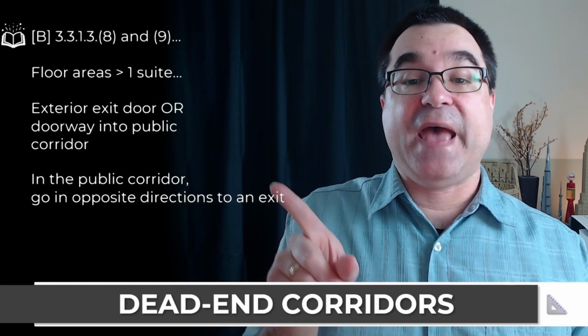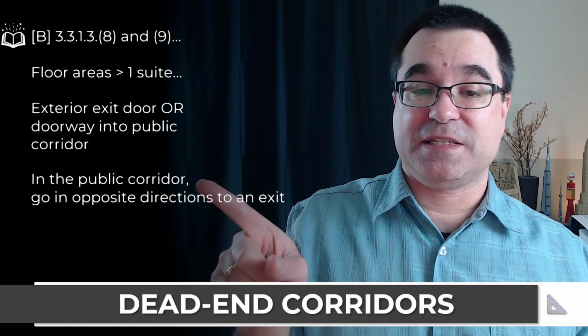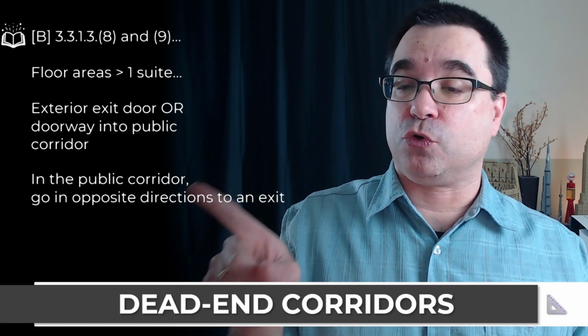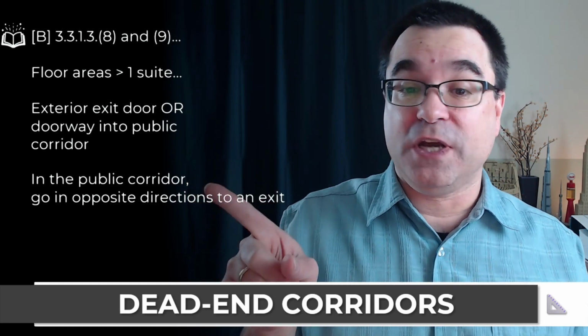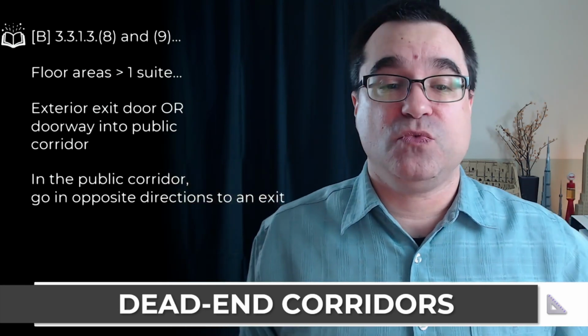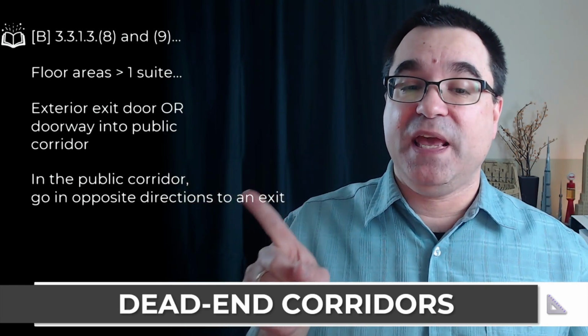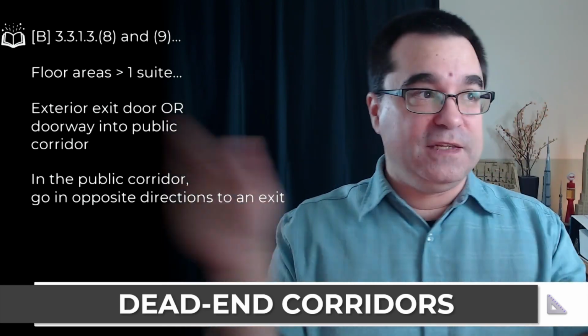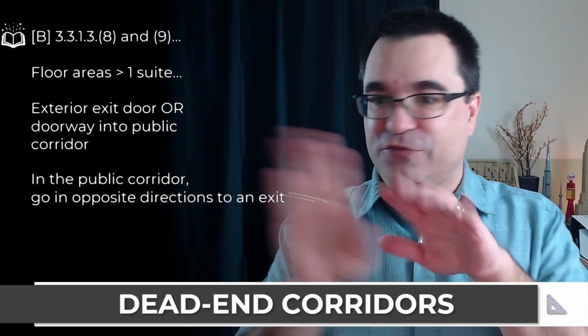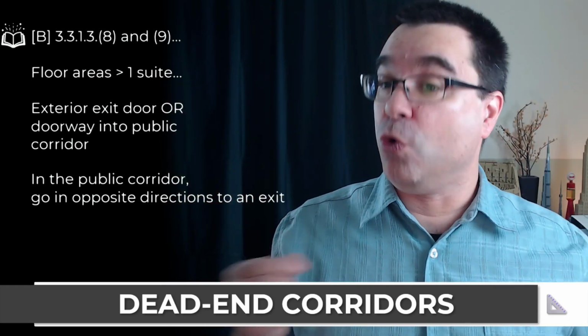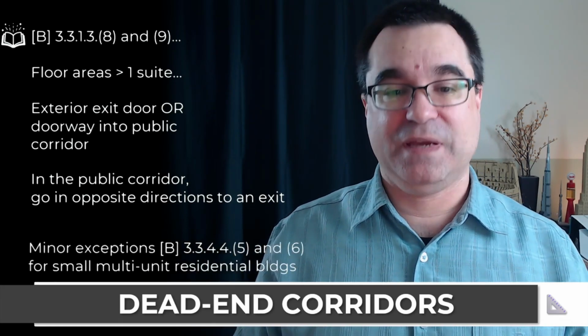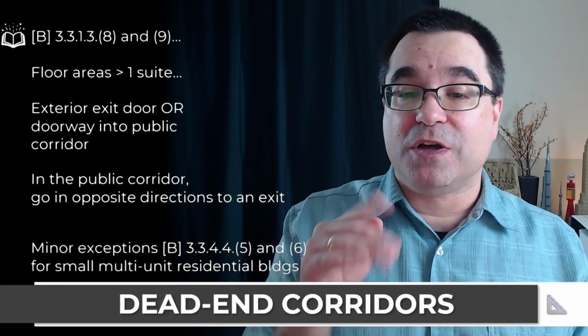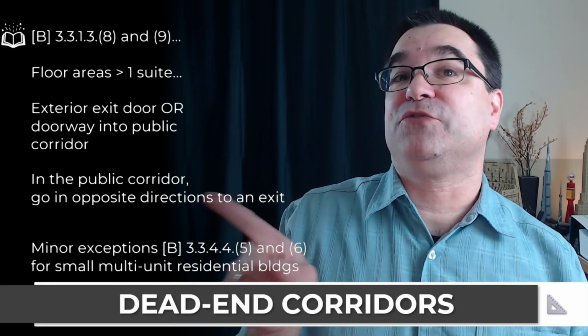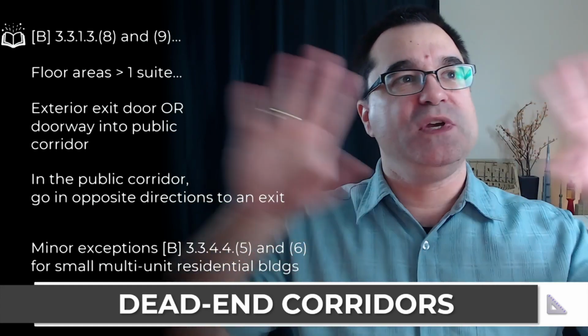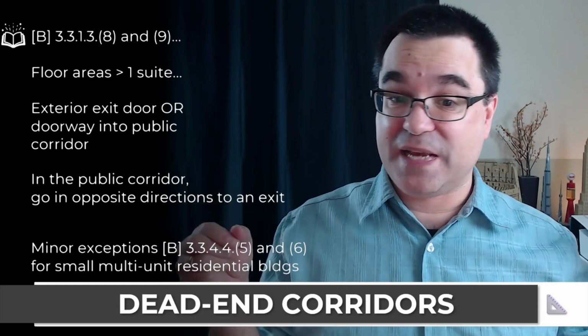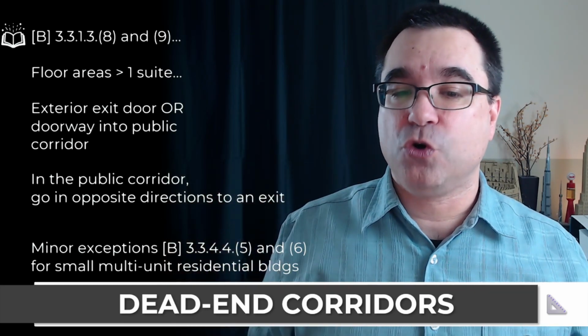And if you do choose to exit that suite into the public corridor, if that is your only option to exit that suite, you must be able to go in any direction in that corridor, so left or right, towards an exit. If that's not possible, if you cannot go left or right as soon as you exit your suite into the corridor towards an exit, you have a so-called dead-end corridor.